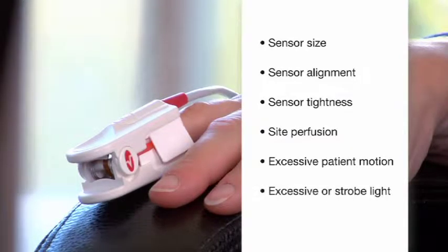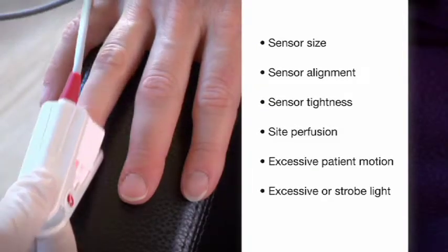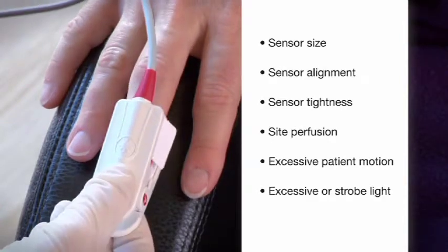Is there interference from bright lights like sunlight or emergency lights? You should cover the sensor to block the light. Again, that's particularly important while a rainbow sensor is self-calibrating. If the readings still seem questionable, get 2 or more readings from different fingers and average them. And remember, it's important to be familiar with your sensor's instructions for use.